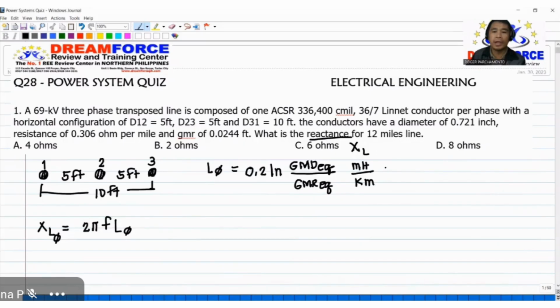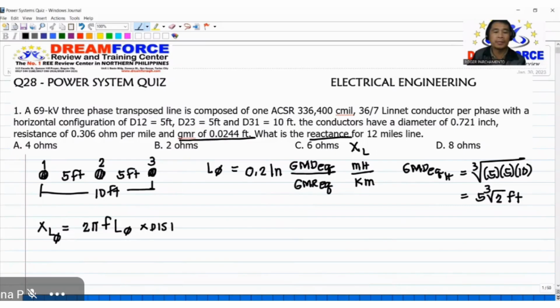Okay, so the GMD for horizontal is equivalent to cube root of 5 times 5 times 10, or equivalent to 5 times cube root of 2 feet. The GMR is already here. Okay, so then multiplied by the distance. That will be 2 pi times the frequency. We will assume 60 hertz as the frequency. Then let's see if there is a correct answer.